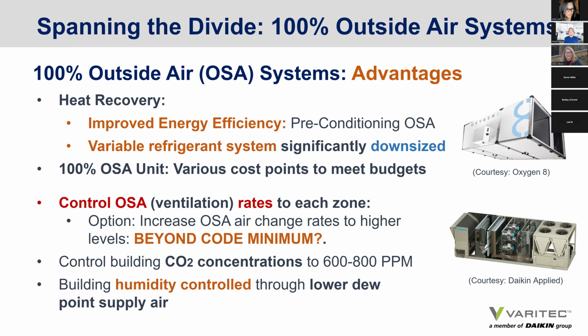So, why do we want, again, to bring energy recovery into a 100% outside air system that's decoupled from the HVAC system? Well, for improved energy efficiency, because you have free preconditioning of the outside air and either cooling or heating. And for 100% outside air variable refrigerant systems, your variable refrigerant system can be substantially downsized and become more efficient. One of the advantages of decoupling the outside air from the mechanical system is you can actually bring the outside air directly into each zone, and it's measurable, it's verifiable.